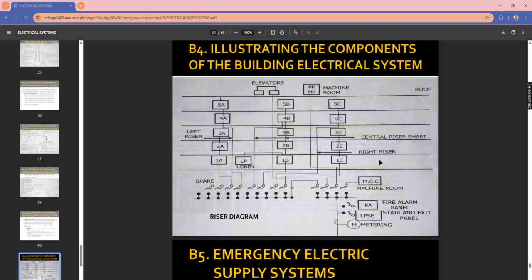Emergency electric supply system. Number one is the emergency system, which provides electric power and illumination essentially for life, safety, and protection, such as lighting for exits, elevators, fire alarm systems, and fire pumps. These must not run out of electrical supply, so those are the demands for the emergency system.